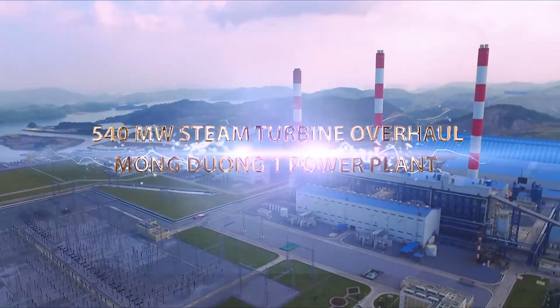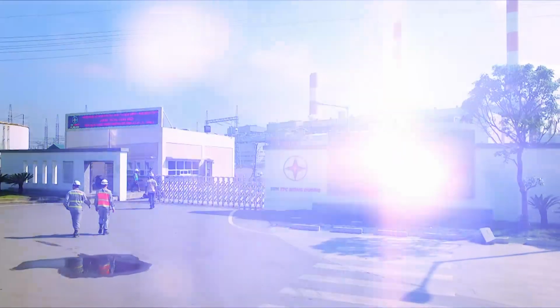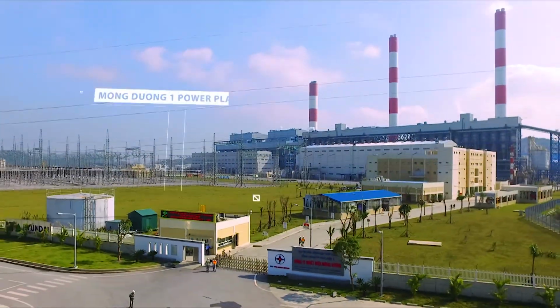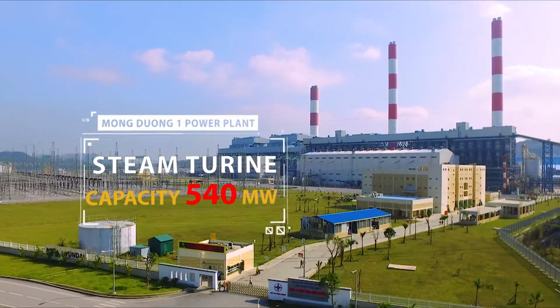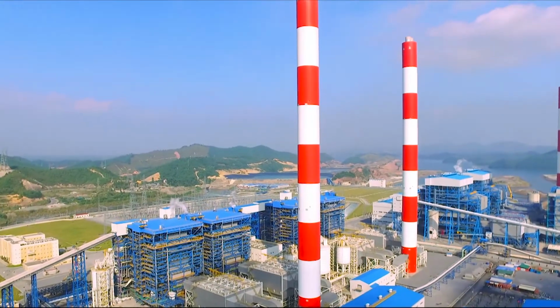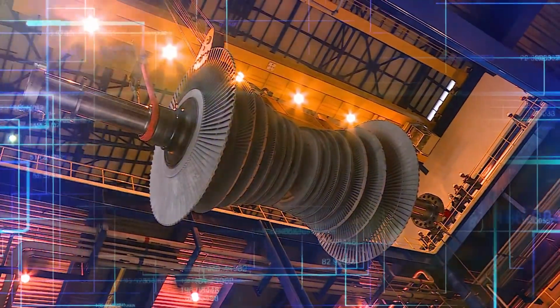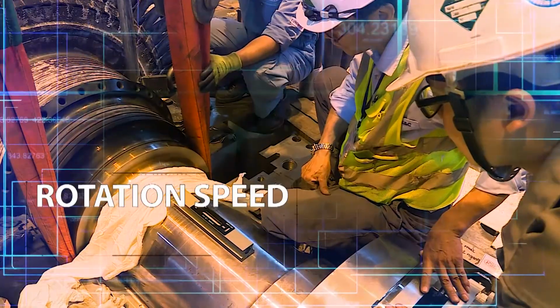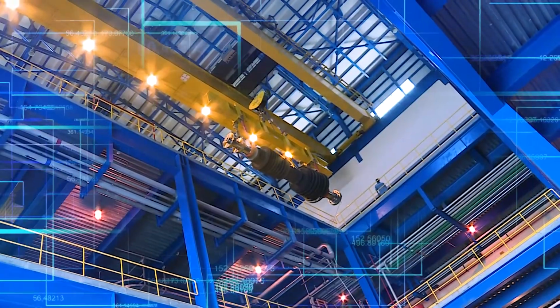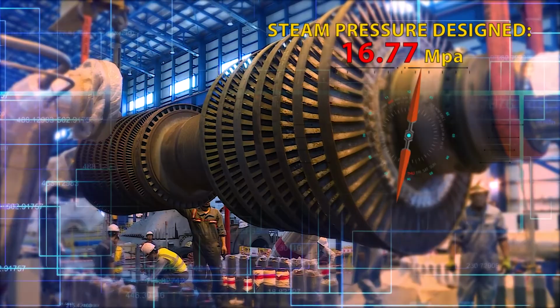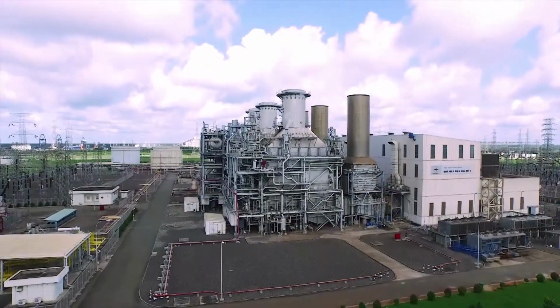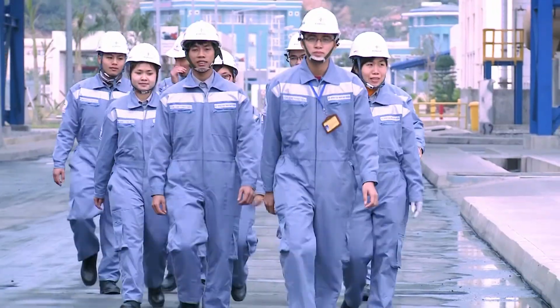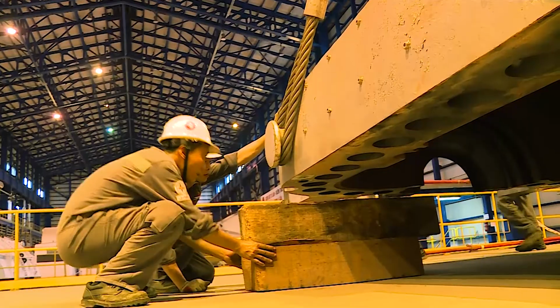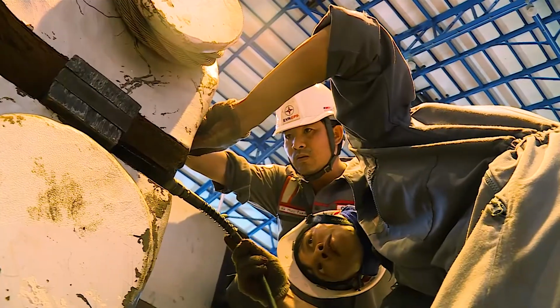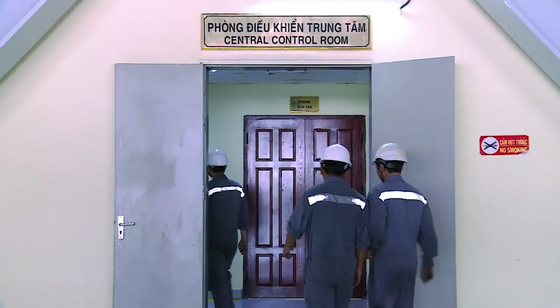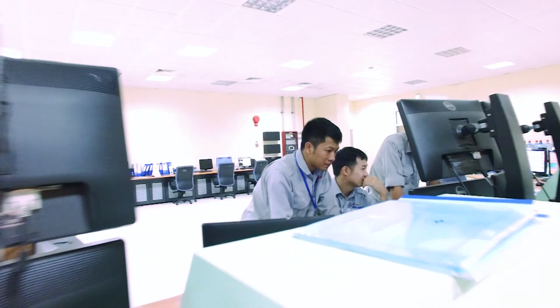The Mong Duong power plant's 540 megawatt steam turbine was manufactured in Korea by Doosan Corporation. It has two low-pressure turbines and one high and intermediate-pressure turbine with a rotation speed of 3,000 rpm, and steam pressure designed at 16.77 megapascal. With more than 20 years of experience in power plant operation and maintenance, EPS provides Mong Duong power plant with overhaul services for steam turbines, enabling stable, reliable, and economic operation.